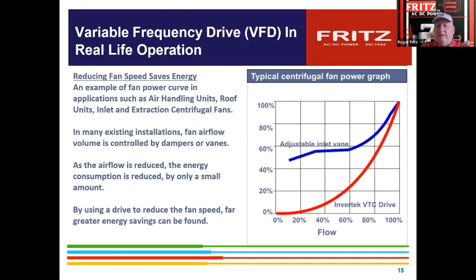So the main factor is that VFDs on fans and pumps were their biggest hit at first, because you get the cube law. If you slow a motor down 20%, the flow only drops 20%, but the actual horsepower drops by the cube factor. It's called the affinity law.